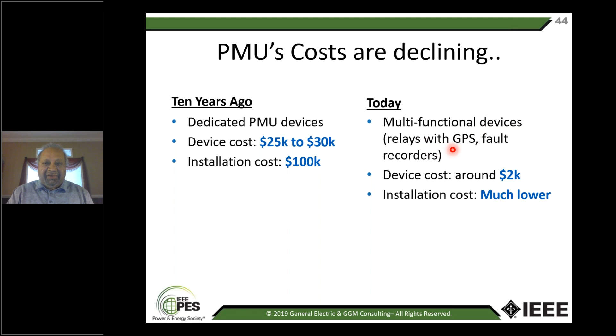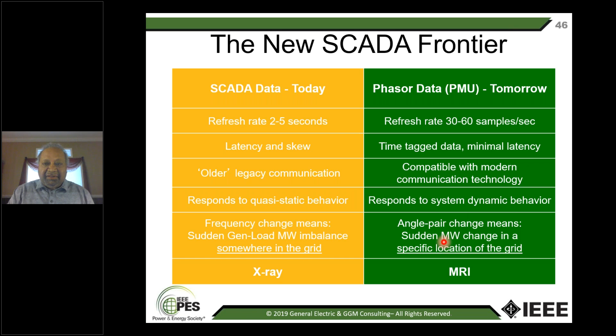So the new SCADA frontier for EMS is, this is the way SCADA has evolved over the past 40 years. Every 2 to 5 seconds, latency and skew, older communication. And a frequency change means there's a problem somewhere in the grid. It may not be in your system, but it's somewhere in the interconnection. And the phasor data of the PMU, which is today and tomorrow, the refresh rate is 30 to 60 samples per second, time tagged, compatible and common modern technology, response to dynamic behavior. And an angle pair change, a PMU angle pair change, means a sudden megawatt change in a specific location in the grid. So earlier information for better decisions. In my 40 years, this has been the first really significant change in EMS technology which has helped benefit grid operations, because over the past 40 years there have been incremental changes, and this is the first step change which will help us.